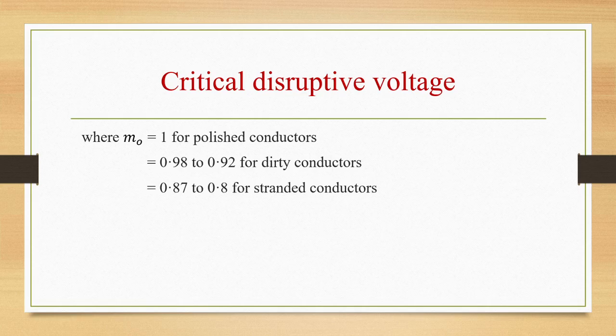So critical disruptive voltage is nothing but the minimum phase neutral voltage at which corona will occur. We have considered two conductors whose radii are r centimeter and they are spaced d centimeter apart. V is the phase neutral potential. The potential gradient is given as g equal to V by r log base e d by r volts per centimeter. In order that corona is formed, the value of g must be made equal to the breakdown strength of the air, and the breakdown strength of air at 76 centimeter pressure and temperature of 25 degrees centigrade will be 30 kilovolt per centimeter maximum, and if you take the RMS value it will be 21.2 kilovolt per centimeter. It is denoted by g naught.